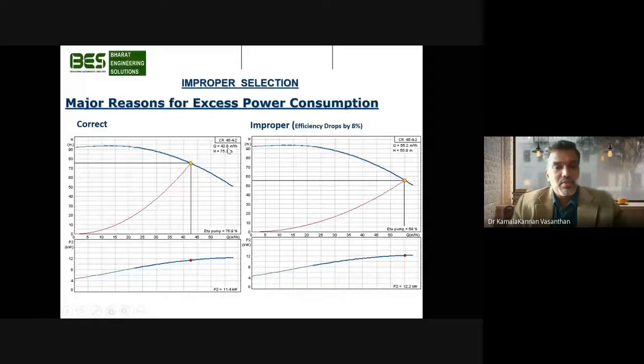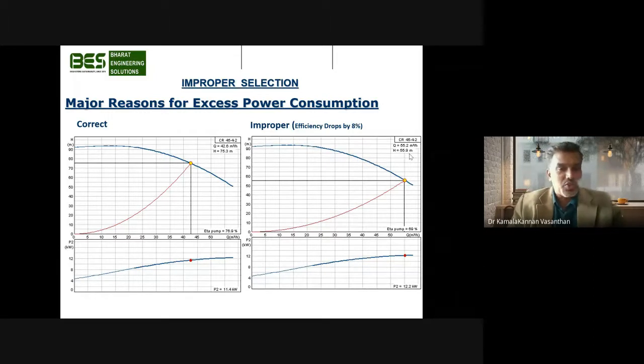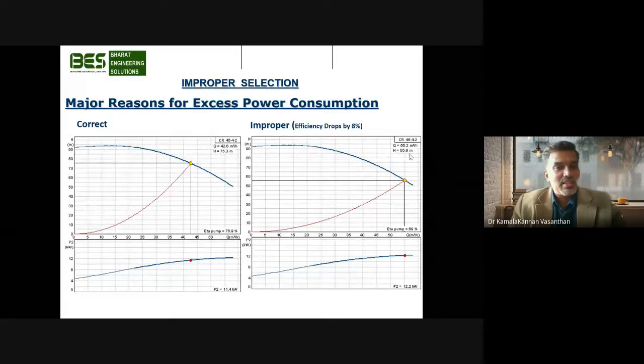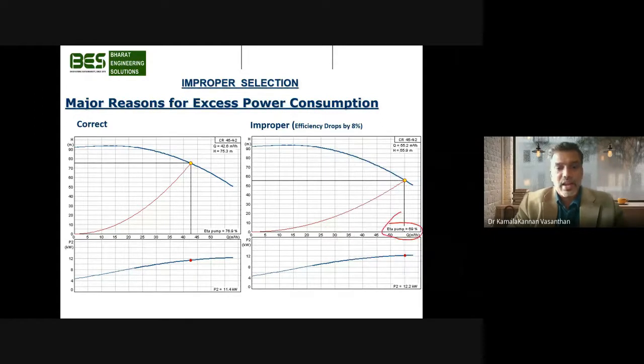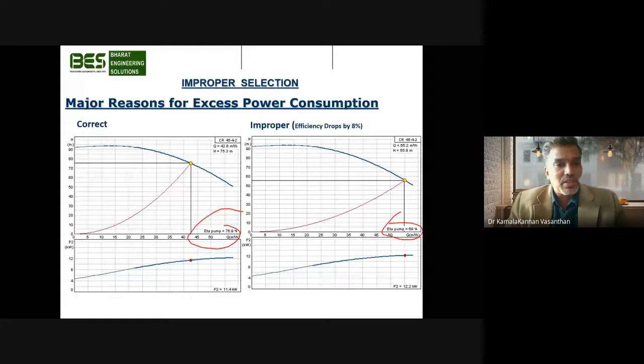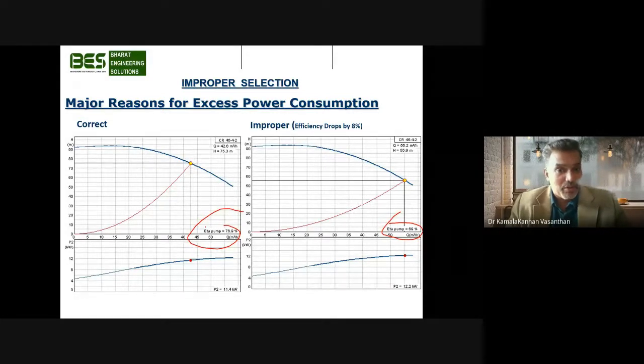The same pump can be operated at a flow and head within the curve region of almost 55 meter cube at 55.9 meters. If this pump is in stock and there's demand from the customer, we still see it getting supplied without explaining that its efficiency is reduced to 69%, against the 76.9% it was actually built for.